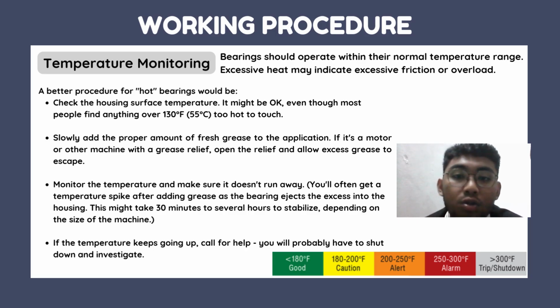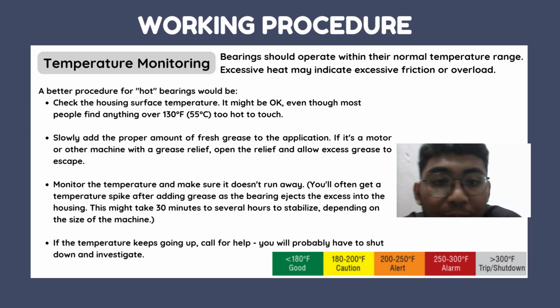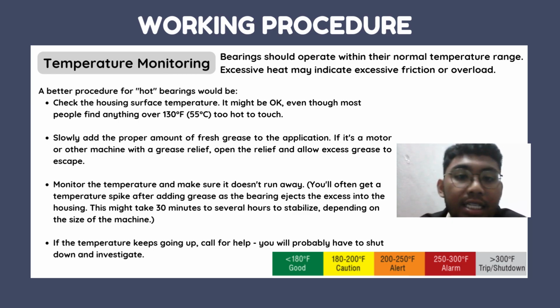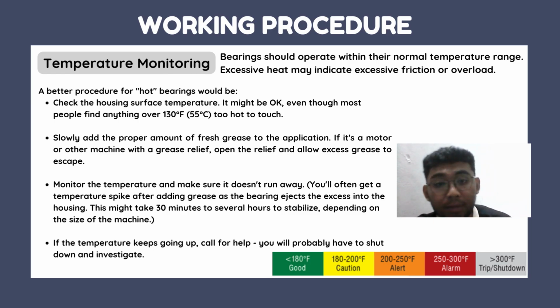Slowly add the proper amount of fresh grease to the application. If it's a motor or other machine with a grease relief, open the relief and allow excess grease to escape. Next, monitor the temperature and make sure it doesn't run away. You will often get a temperature spike after adding grease as the bearing ejects the excess into the housing. This might take 30 minutes to several hours to stabilize, depending on the size of the machine. The last one is if the temperature keeps going up, call for help. You will probably have to shut down and investigate.